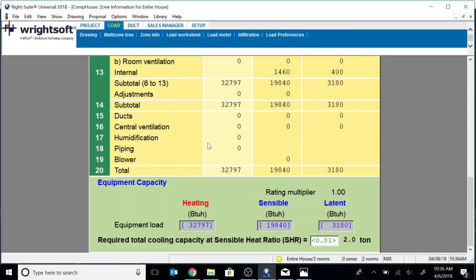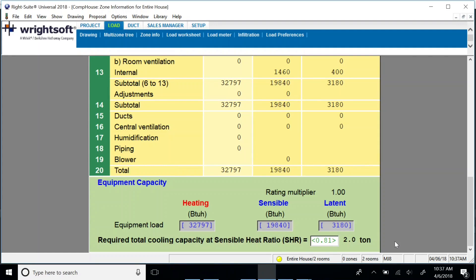What we have here: this is our heating load, this is our sensible cooling load, and this is our latent cooling load. I adjusted the rating swing multiplier to one, and I also adjusted the sensible heat ratio from 0.70, which is standard, to 0.81. Because what I actually did was I went and looked at the expanded performance data on a piece of equipment I'm thinking about using, and I was able to verify that at these indoor conditions I can reach my latent heat and sensible heat requirements. So I entered that, and it tells me it needs a two ton.